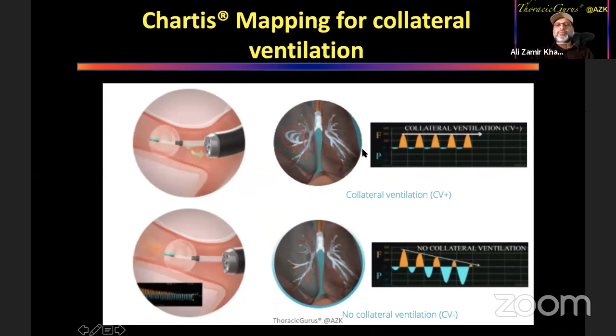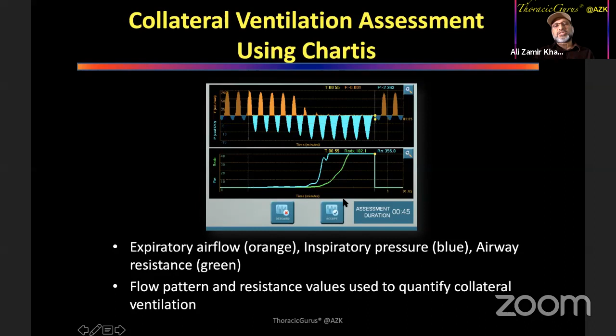The expiratory airflow is orange. So the top part is orange. The inspiratory pressure is blue, okay? And the airway pressure is green. So whenever you inflate the balloon, no air will come out. So expiration should stop. Okay, but inspiration continues going there. So no air is coming out, and most importantly, the airway pressure is going up. So orange goes away, the green increases in size, but the resistance goes up as well.